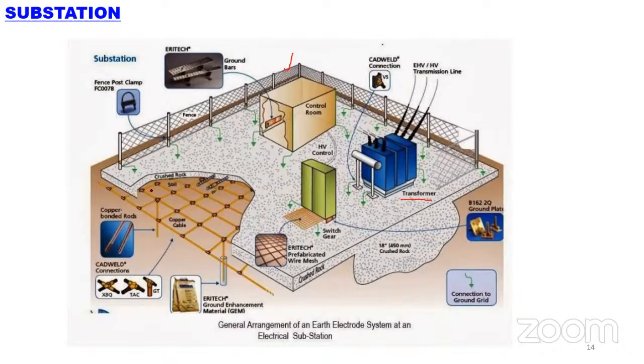Below ground, 1 or 2 feet down, we place a conductor called the earthing conductor. In high voltage substations, when you dig the ground, you find a lot of conductor below, placed at 1 or 2 feet with required spacing, which helps minimize step and touch potential.